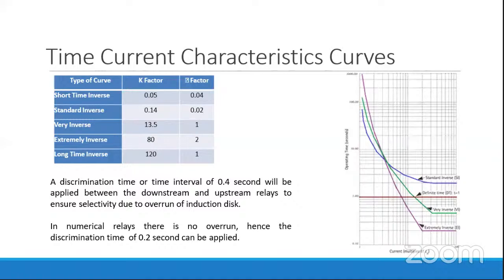Earlier, the time discrimination was defined as 0.4 seconds, that is 400 milliseconds, to be applied between downstream and upstream relays in order to ensure selectivity, due to the overrun of the induction disk. It means that in earlier times protections were taken care of by electromechanical relays which have an induction disk. This was sluggish in operation and took more time to operate, so the time grading was given as 0.4 seconds.